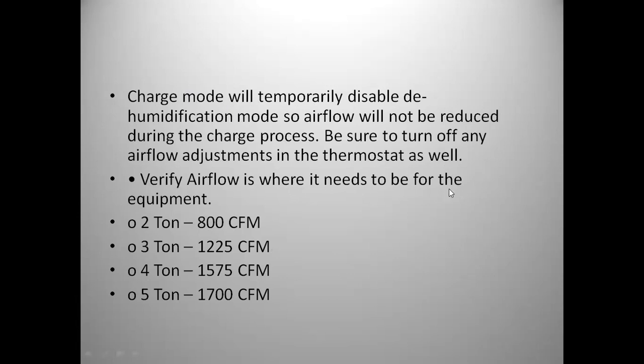Do verify airflow is where it needs to be for the equipment. This can also be done at the EcoNet. So from the EcoNet status screen, you can check your airflow CFM. You can also check on the same screen your static pressure. So if you have a 2-ton unit, you should be around 800 CFM, 3-ton, 1225, 4-ton, 1575, and 5-ton, 1700. So once you put it in charge mode, check your airflow, check your static pressure.